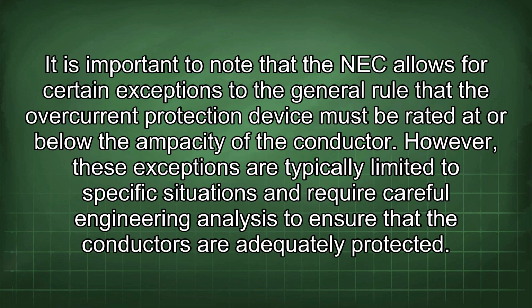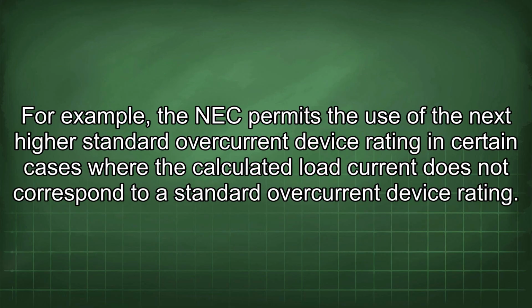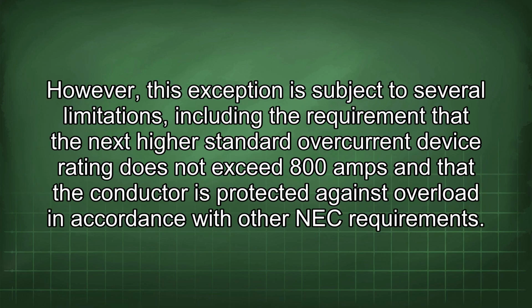It is important to note that the NEC allows for certain exceptions to the general rule that the overcurrent protection device must be rated at or below the ampacity of the conductor. However, these exceptions are typically limited to specific situations and require careful engineering analysis to ensure that the conductors are adequately protected. For example, the NEC permits the use of the next highest standard overcurrent device rating in certain cases where the calculated load current does not correspond to a standard overcurrent device rating. However, this exception is subject to several limitations, including the requirement that the next highest standard overcurrent device rating does not exceed 800 amps and that the conductor is protected against overload in accordance with other NEC requirements.